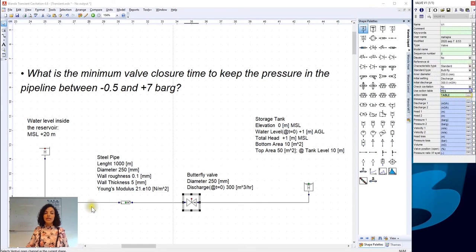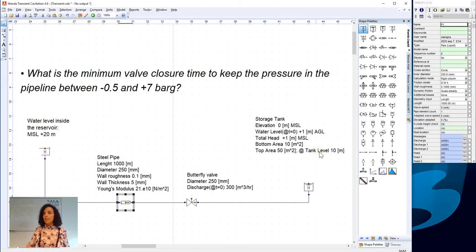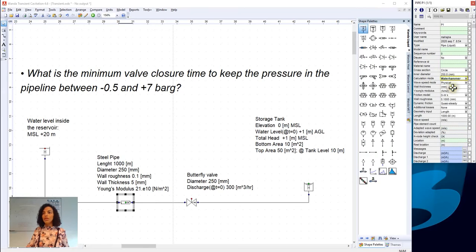Now, we want to update the wave speed value in the pipeline system. So, here, instead of having the calculation mode at rigid column, we use water hammer. And we insert our values. So, for wall thickness, we insert 5 millimeters. And for Young's modulus, we insert 21 times 10 to the power of 10. And if we look, the calculated wave speed in Wanda is equal to 1183 meters per second, as we have calculated from before.